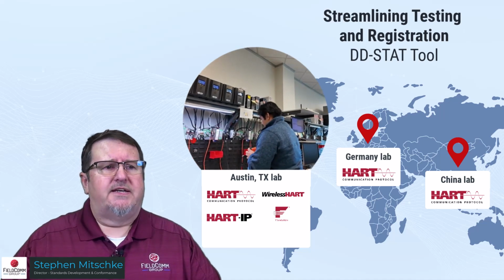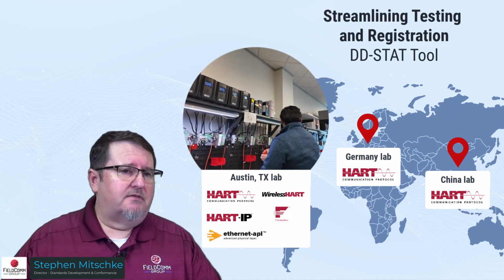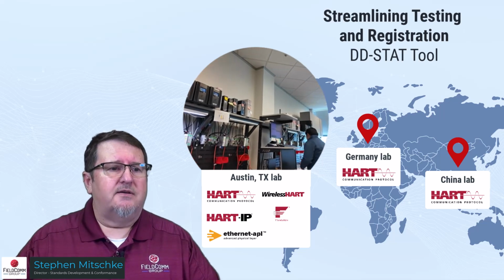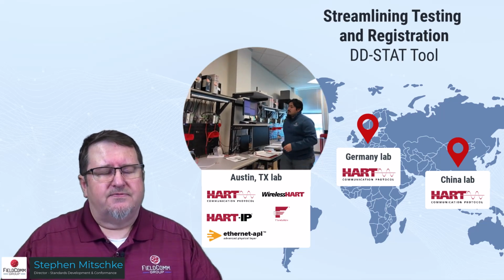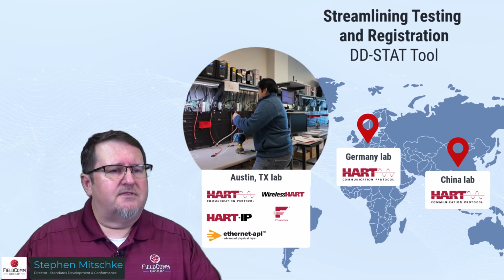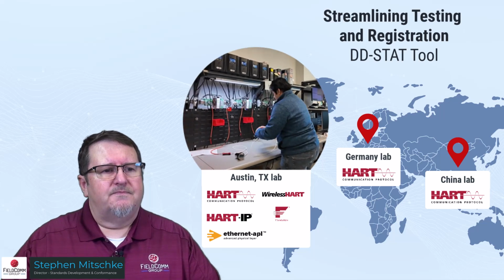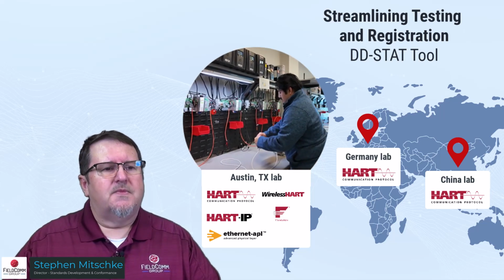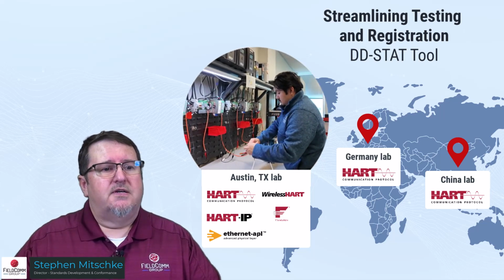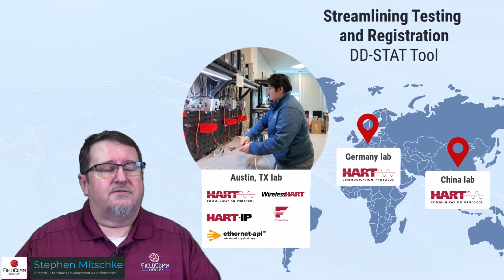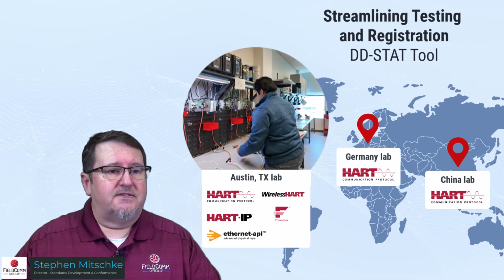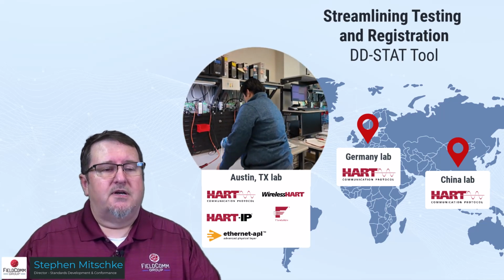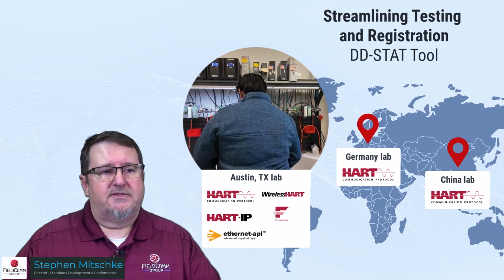Relatively new to our testing is Ethernet APL. Now, Ethernet APL is a physical layer. We now have successfully run registration campaigns for field switches. So we can do the switches just fine. We can also, and we have successfully run campaigns on field devices. Now remember, it's a physical layer. We're only testing the physical layer aspects.